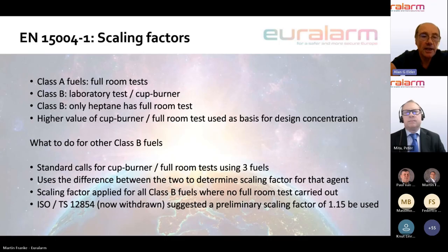In the event that a scaling factor is not available for the Class B fuel, in other words, when no full room test has been carried out, the standard suggests a preliminary scaling factor of 1.15. So if you only have a cup burner value for a particular material, then the standard recommends that you apply a 15% uplift to that cup burner value. That would not apply to heptane because heptane already has a cup burner and a full room test concentration specified. But if you have another Class B fuel where the full room test has not been carried out, then the standard would actually suggest a preliminary scaling factor of 1.15.